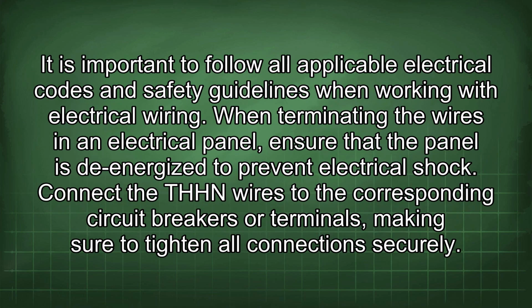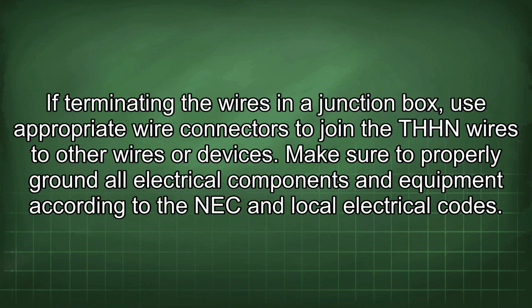terminals. It is important to follow all applicable electrical codes and safety guidelines when working with electrical wiring. When terminating the wires in an electrical panel, ensure that the panel is de-energized to prevent electrical shock. Connect the THHN wires to the corresponding circuit breakers or terminals, making sure to tighten all connections securely. If terminating the wires in a junction box, use appropriate wire connectors to join the THHN wires to other wires or devices. Make sure to properly ground all electrical components and equipment according to the NEC and local electrical codes.